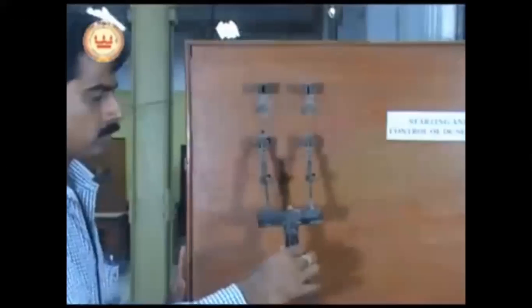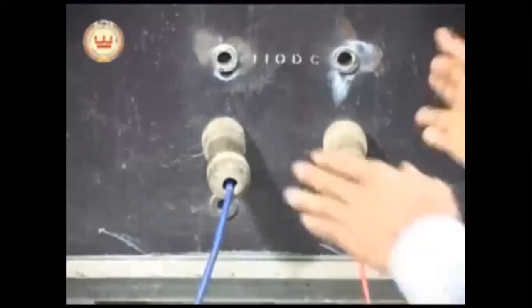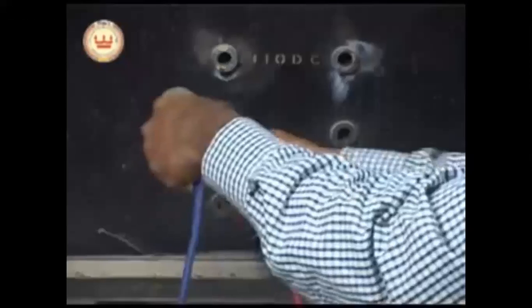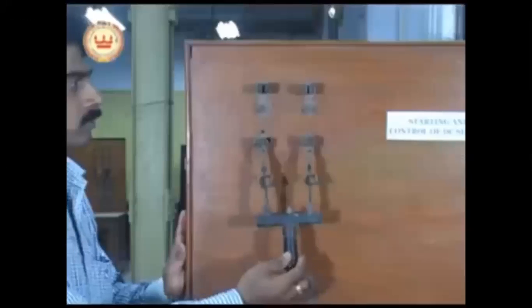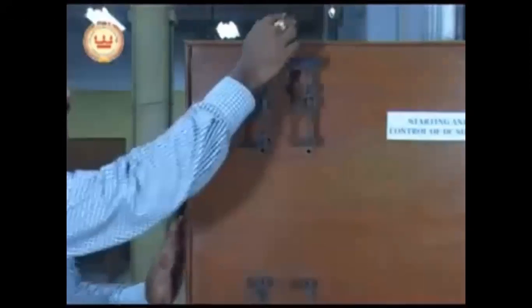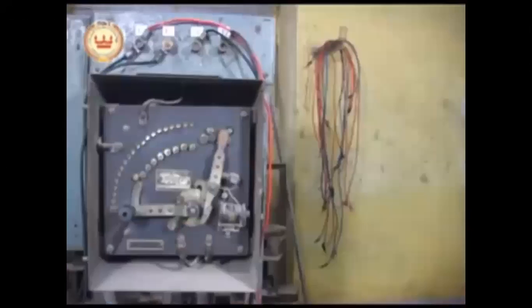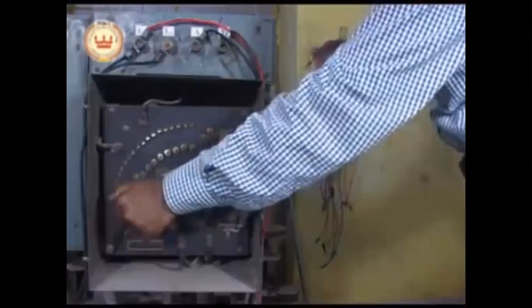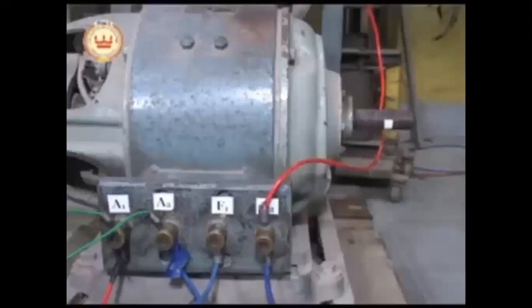Now switch off the supply. Interchange the supply terminals. Again switch on the supply. Run the motor by the starter. Observe the direction of rotation, whether it is being changed or not.